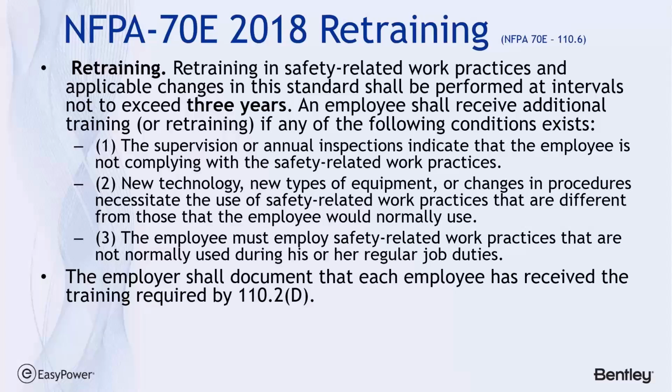And this compared to the recalculations of the model is recommended only every 5 years or anytime there's a change in the system that affects the energy. So the important point is better training and better awareness of the hazards and how to recognize them go a long way in preventing arc flash hazard problems.